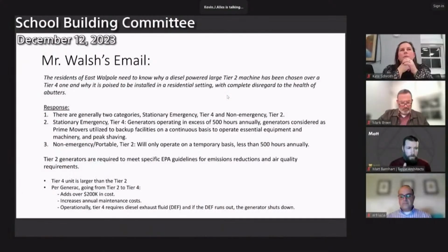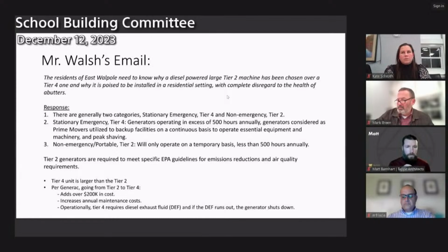No, essentially when power is lost, everything shown on that equipment list will be on emergency generator power. So the emergency lighting, your fire alarm systems, your security systems, the kitchen equipment, everything will be able to run. Again, the mechanical systems will be able to run as they are sequenced through the building management system.